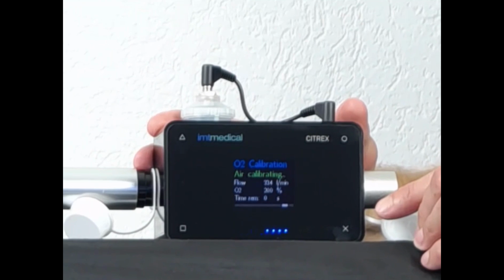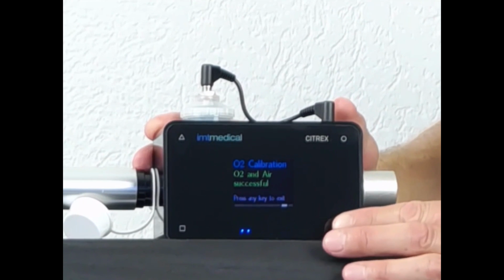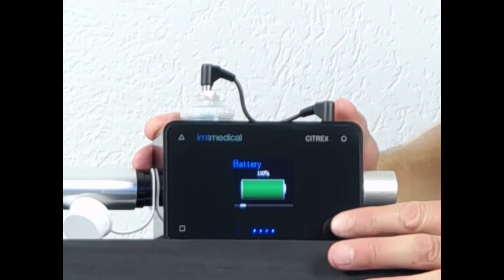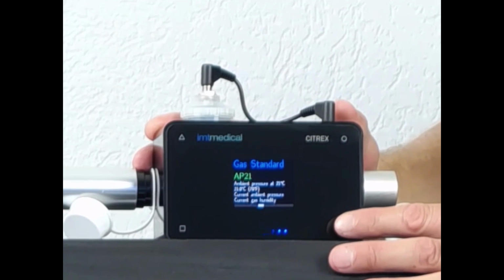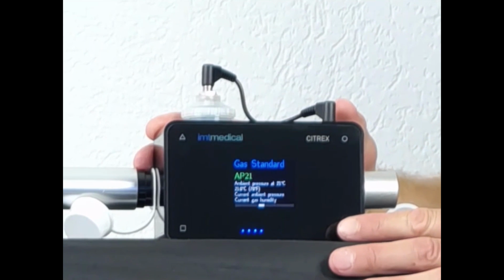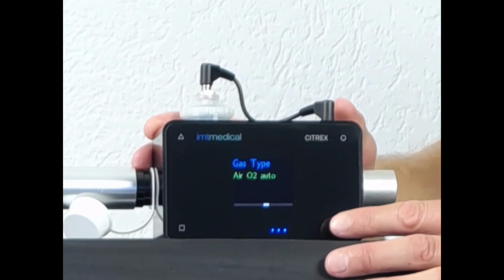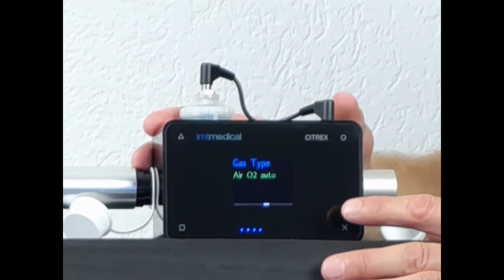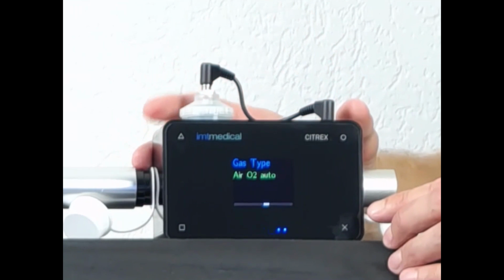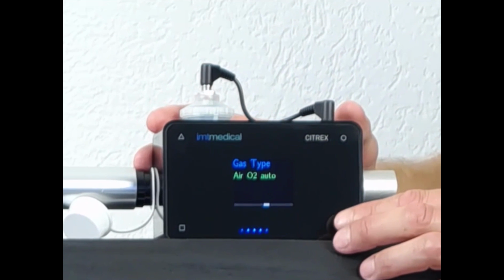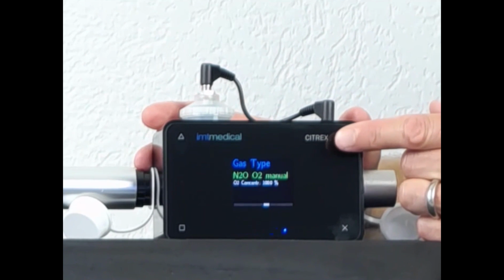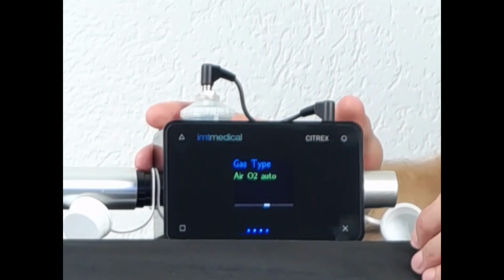As a next step, we want to quickly double check on the gas type. So we click here on the service menu, we click through until we find the gas standard, AP21. This AP21 is matching up with the ventilator I'm calibrating. Then the gas type is air with automatic oxygen measurement. So the oxygen cell we just calibrated is being used to detect the gas type. We could also change that. We could have nitric oxide and many other gases, CO2, air only, air and manual adjustment of oxygen, and the most convenient one is air and oxygen automatic, which is typically used for ventilators and for anesthesia machines.